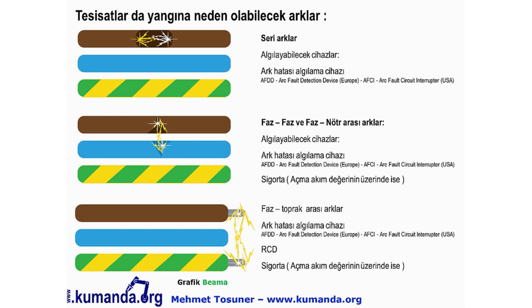Paralel arklar faz-faz veya faz-nötr arasında oluşur; bunları algılayacak olan cihazlar ark hatası algılama cihazı ya da sigorta/MCB'dir. Ancak sigortanın algılayabilmesi için ark akımının açma akım değerinin üzerinde olması gerekir. Ark hatası algılama cihazları AFDD elektronik cihazlardır; akım geçişindeki sıçramalar ve titreşimler üzerinden devrede ark olduğunu yorum getirip açma yaparak koruma sağlar. Özellikle petrokimya, patlayıcı/parlayıcı gaz ortamları ve müze gibi değerli eşyaların bulunduğu yerlerde kullanılır.